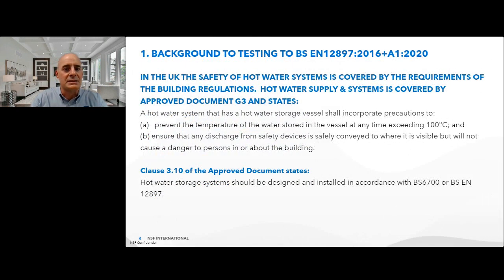The background to the testing then to EN 12897. So in the UK, the safety of hot water systems is covered by the requirements of the building regulations. Hot water supply and systems is covered by the approved document G3. This states, a hot water system that has a hot water storage vessel should incorporate precautions to A. Prevent the temperature of the stored water in the vessel at any time exceeding 100 degrees C, and B.